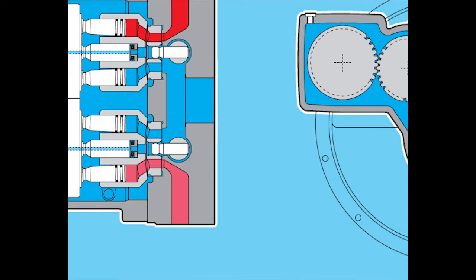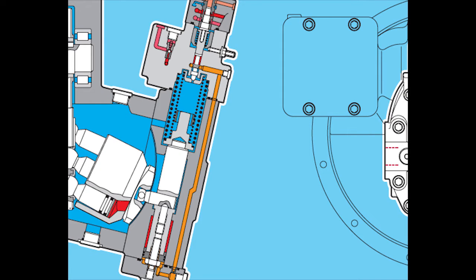Individual Power Controller With Power Override by Pilot Pressure and Hydraulic Stroke Limiter Negative Control LA0, LA1. On the variable double pump with individual power controller LA0/LA1, the two rotary groups are not mechanically coupled, i.e. each rotary group is fitted with a separate power controller. The power controller controls the displacement of the pump depending on the operating pressure so that a defined input power is not exceeded.